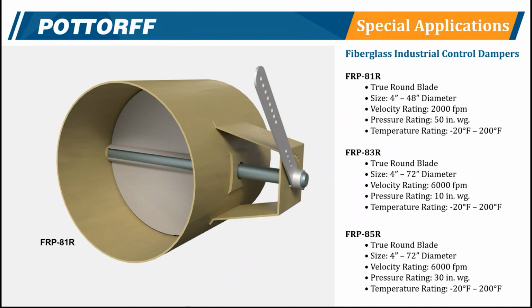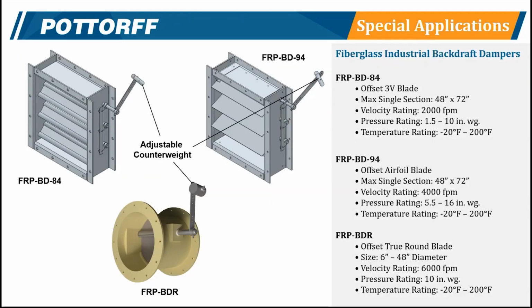For those, we do have stainless steel for whenever corrosion may be an issue. 316 is probably your better bet for most standard corrosive environments. So our standard industrial round dampers or rectangular dampers may be a better option to be a bit more competitive. We've got backdraft damper lines through the fiberglass lines as well, whether they're round or rectangular. So we've got offset 3V blades, offset airfoil blades, and an offset true round blade that's squared off with the BDR. Following our standard conventions, the 80 series are typically going to be our triple V lines. The 90 series are going to be airfoil lines, and then we're going to have an R in there for the round.